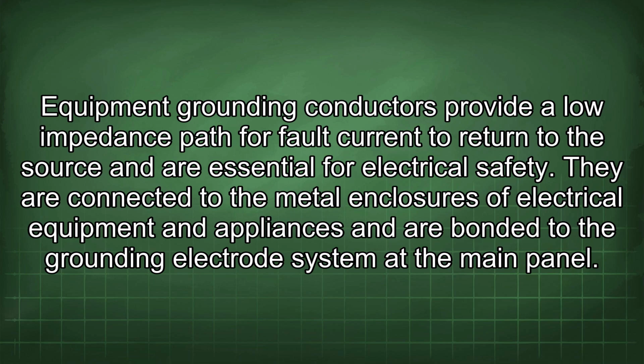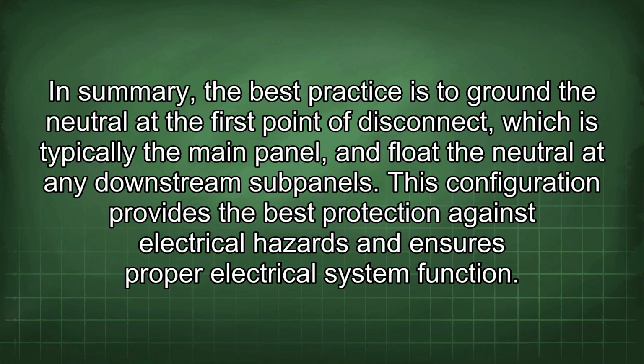They are connected to the metal enclosures of electrical equipment and appliances and are bonded to the grounding electrode system at the main panel. In summary, the best practice is to ground the neutral at the first point of disconnect, which is typically the main panel, and float the neutral at any downstream subpanels. This configuration provides the best protection against electrical hazards and ensures proper electrical system function.